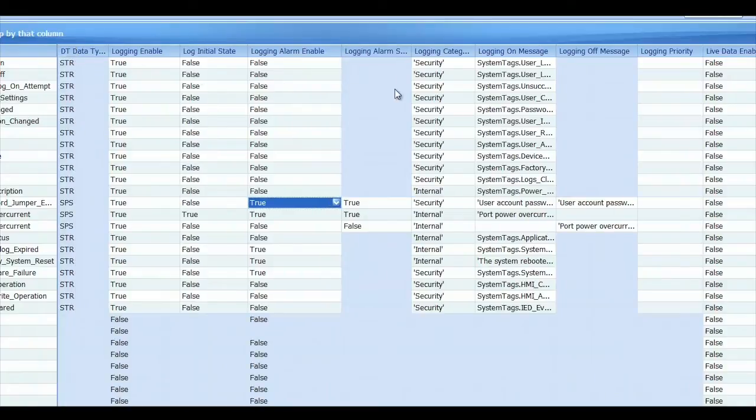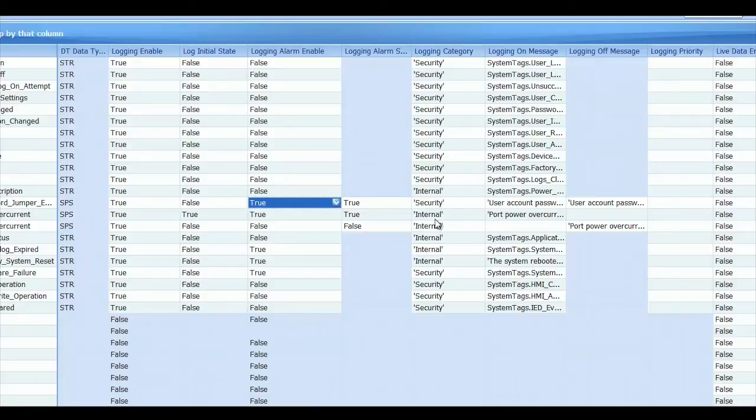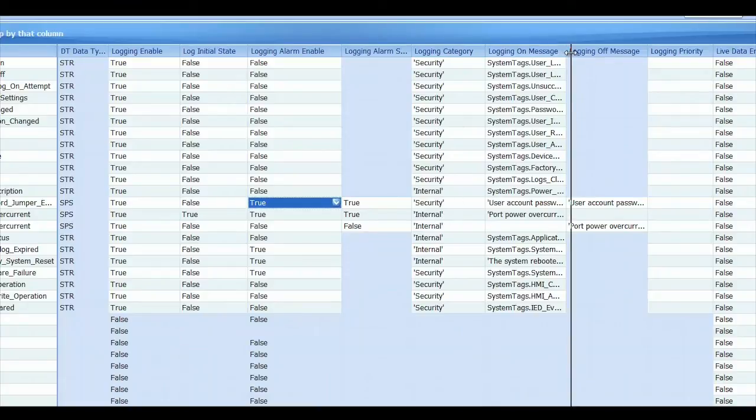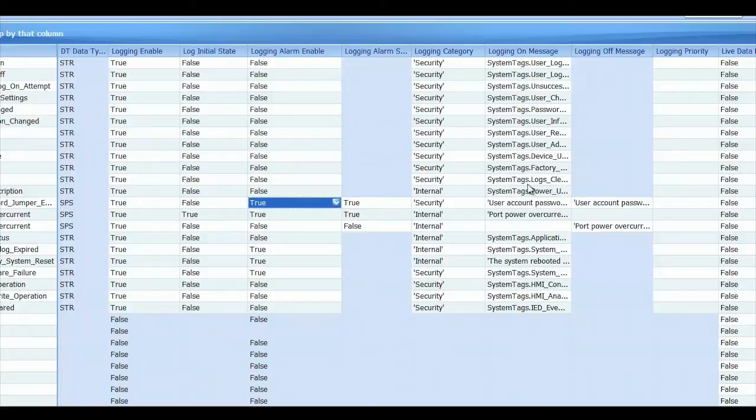There's logging categories, which is any string value that you put in there. The default ones are security and internal, but you can make up any that you want. And there's also a logging on message and a logging off message. The logging on message is when the value is true in a state that it needs to be logged, then that's the message that will log. When it's not in that state, then it will log the other message. If the message is blank, it just won't log anything.